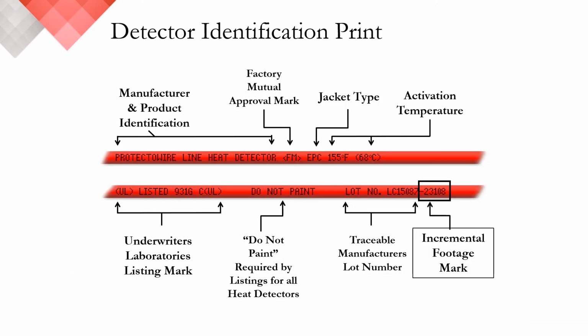Both types of Protectowire, the PHSC series as well as our CTI series, have a consistent format for their outer jacket printing as shown here. There are small changes to account for different model numbers and jacketing materials. However, because we are an ISO 9001 registered company, each detector has the lot number printed every 24 inches, or approximately 60 centimeters, and there is also an incremental length mark at the end of the reoccurring print job. I highlight this information as it is remarkably helpful for facility owners as well as field service technicians to understand exactly how much detector is on a particular zone.